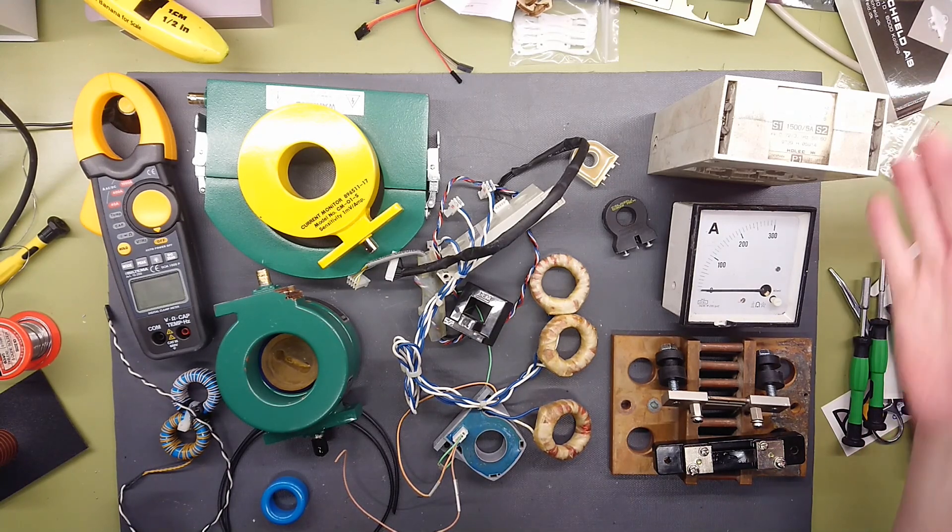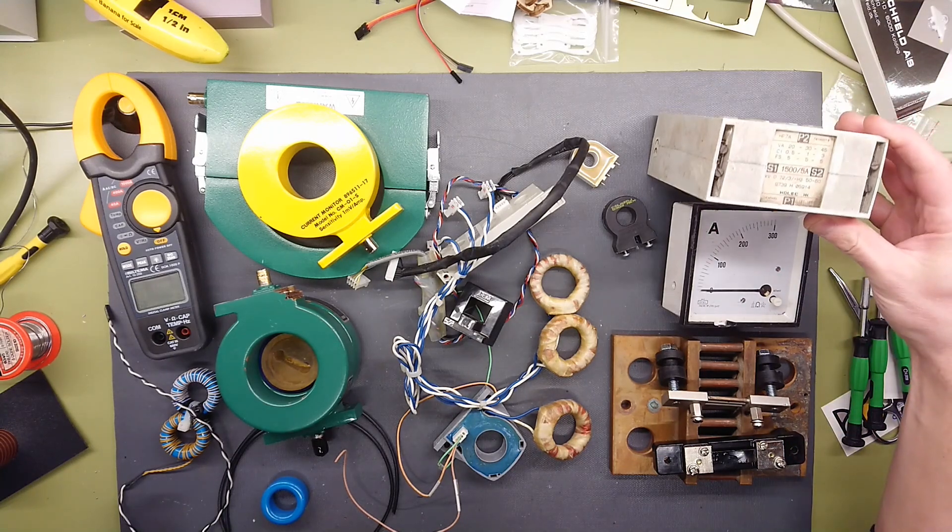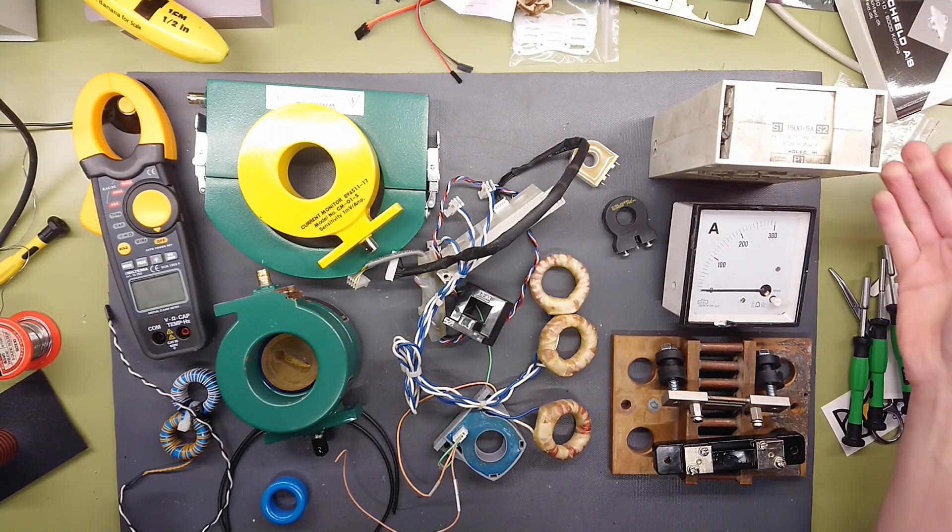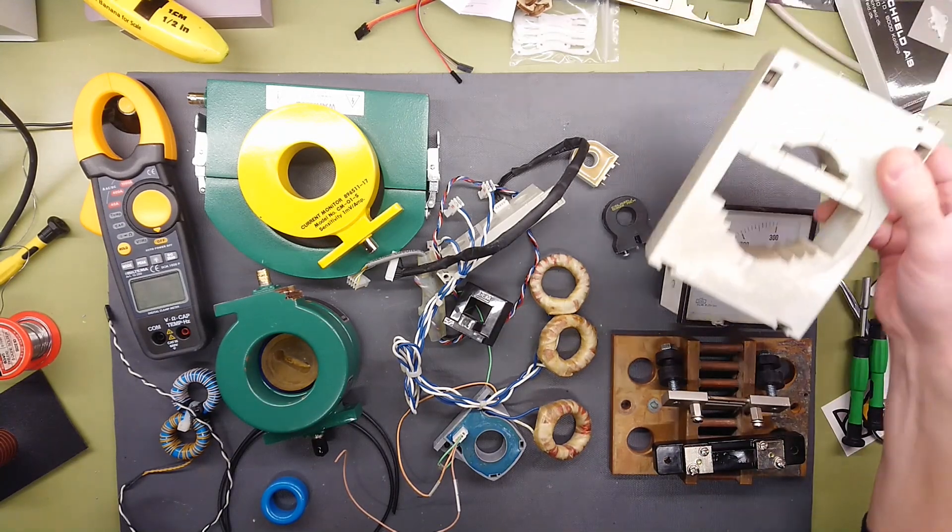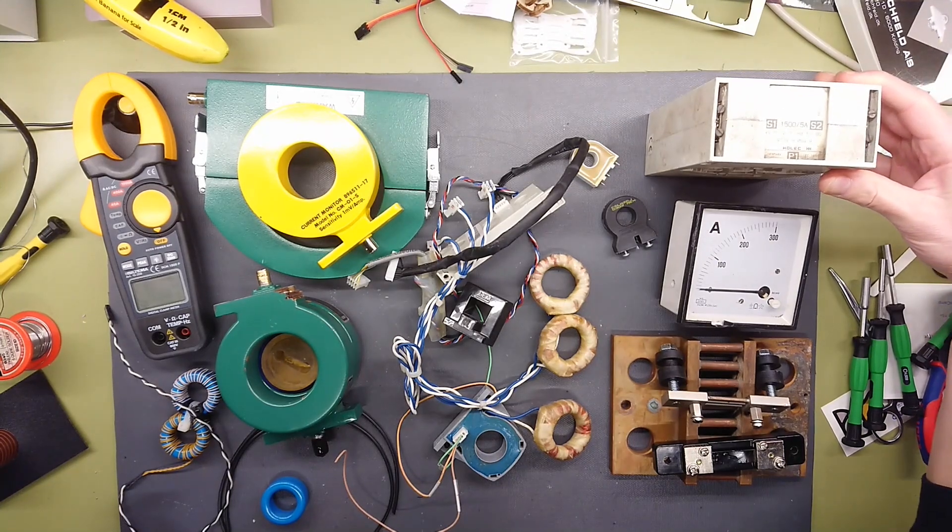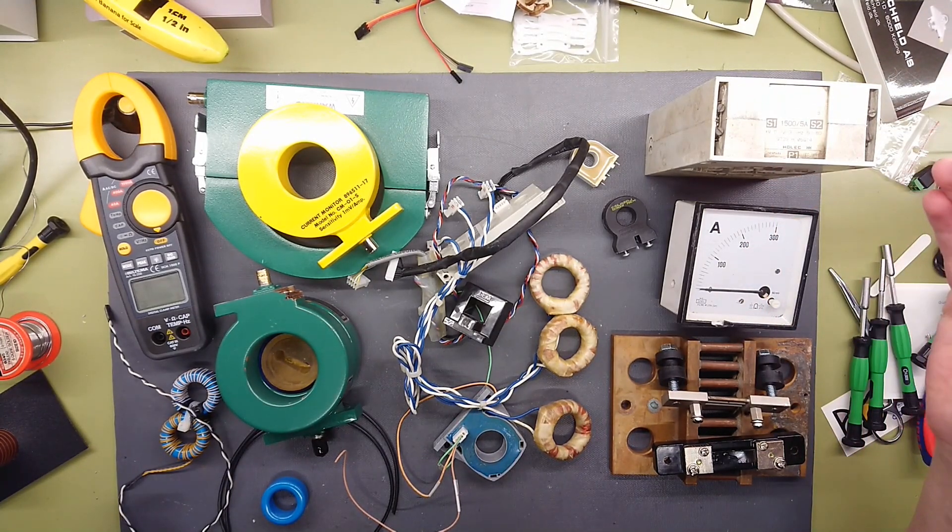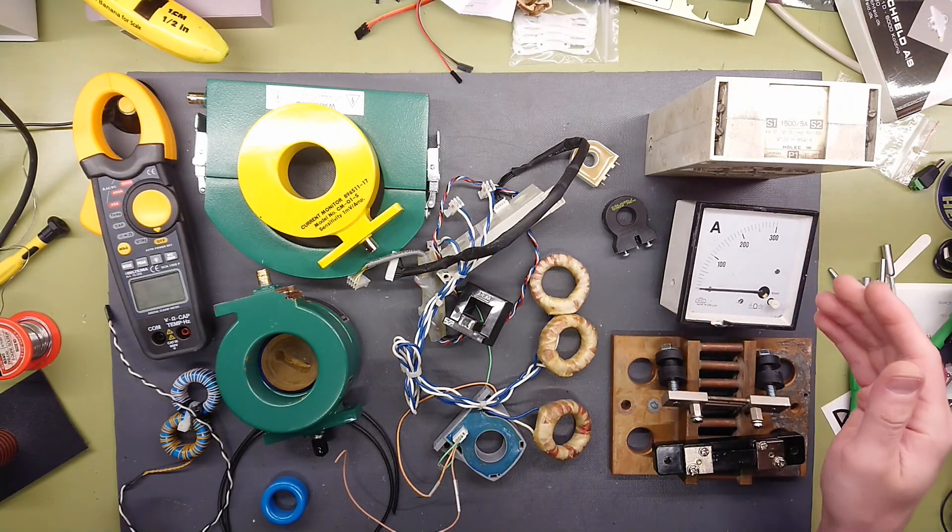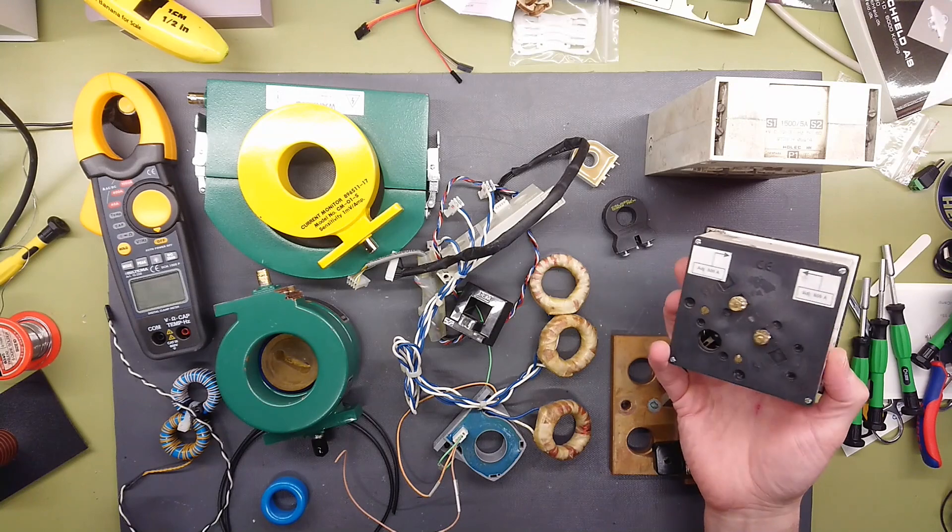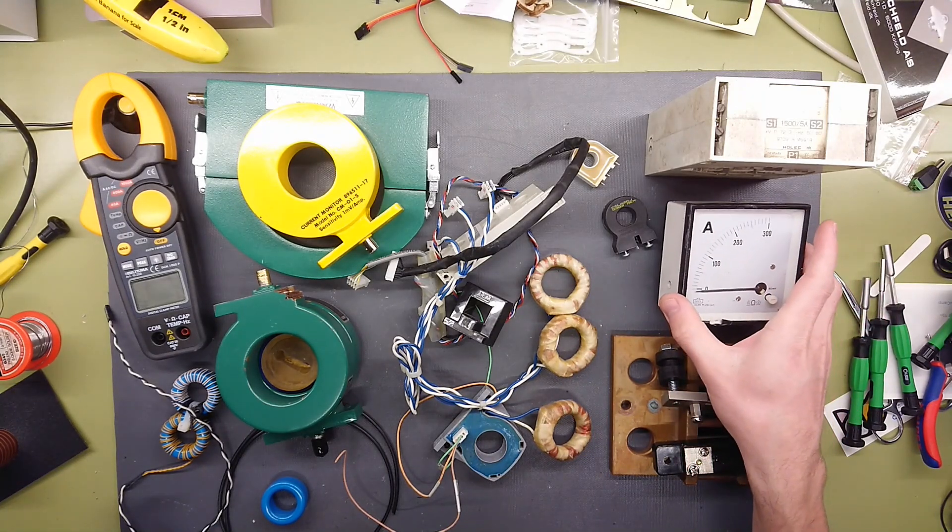Over here in what we can call the old-school section is where we have the good old big current transformers that just transform current from a large one that goes through the middle of this transformer. It has a ratio 1500 to 5 amps, and that is because it's a standard that a very large amount of these current meters that you can find are rated for a 5 amp current input.